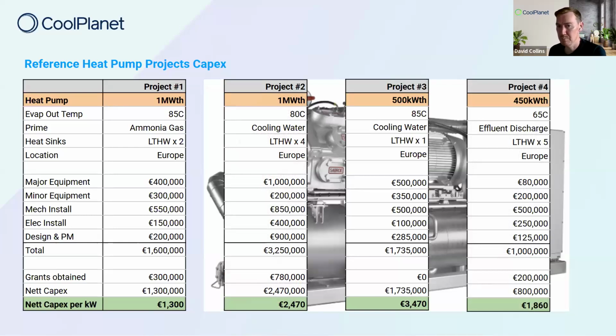All of them are low temperature heat pump projects. So you can see there that they're producing hot water at a temperature of between 65 to 85 degrees C. But actually, very importantly, they're using different sources of prime for the heat pump. So this first one here is ammonia gas. So this heat pump is interfacing directly with the discharge gas on a refrigeration system. It's in a brewery, and it's taking that gas and absorbing it into the heat pump to produce hot water.